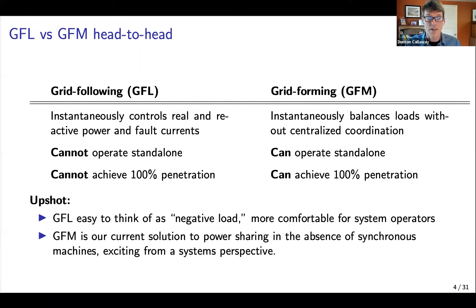So the upshot then is that it's easy to think of a grid following converter just as like a negative load. If you're a power system operator, it's out there, you know pretty well what it's going to do. It's going to deliver some real and reactive power amount. It's not going to provide fault current to any large degree. Whereas a grid forming converter is our current solution to power sharing in the absence of a synchronous machine. So if we want to have 100% power electronic converter based grids, we need some amount of grid forming converters. There are a lot of exciting system level perspective reasons to be thinking about grid forming converters and a lot of interesting challenges to solve, and I'm going to talk about some of those today.